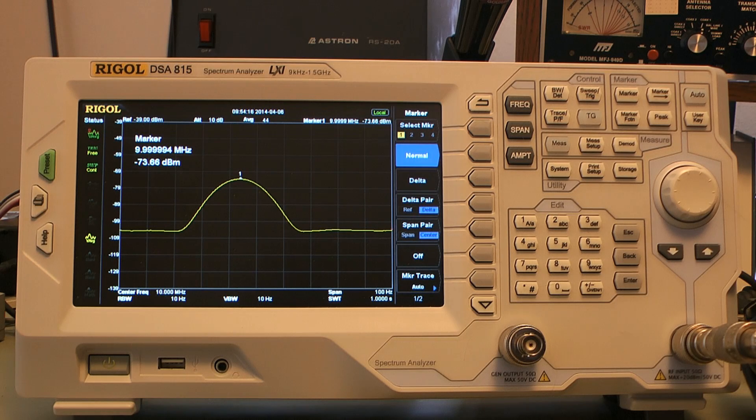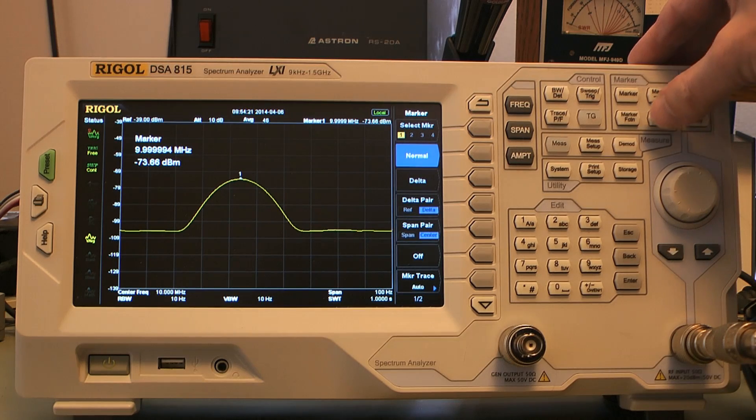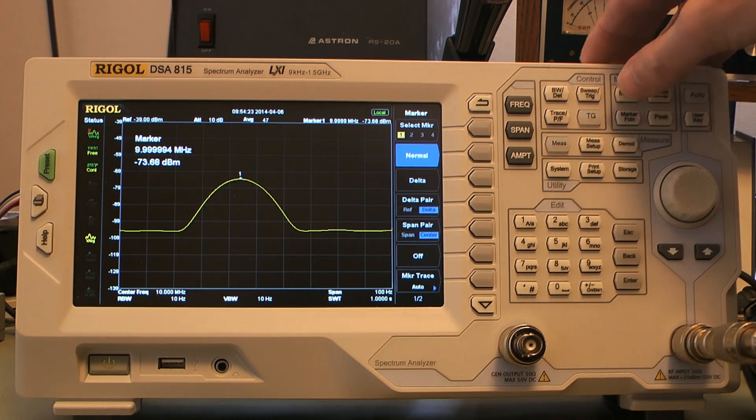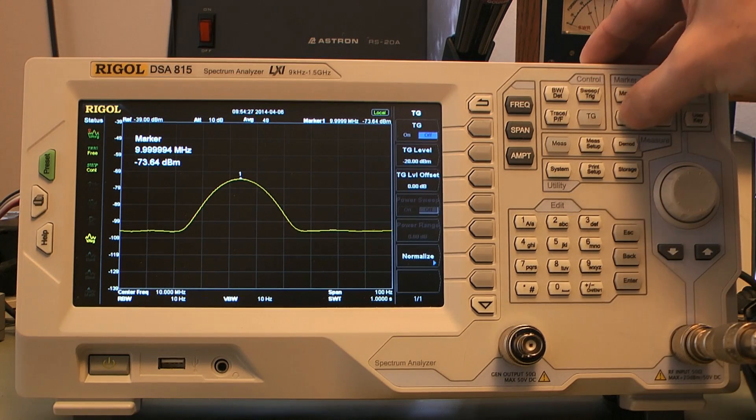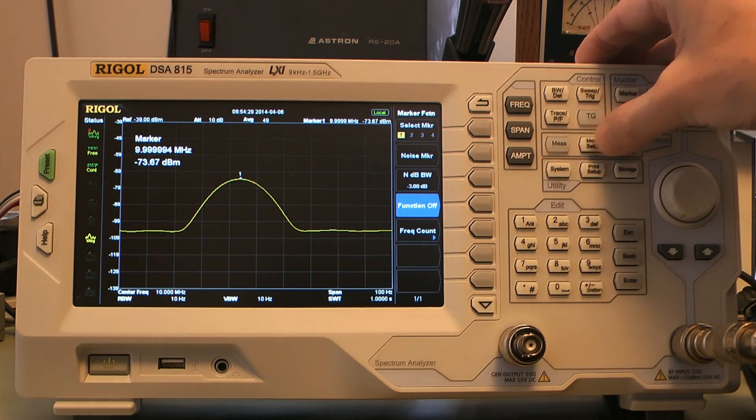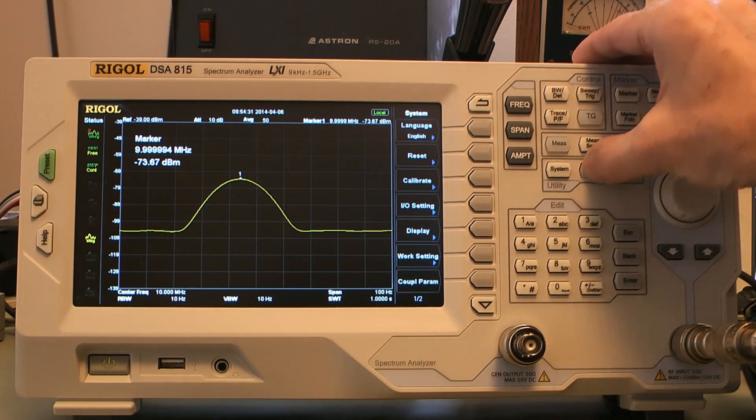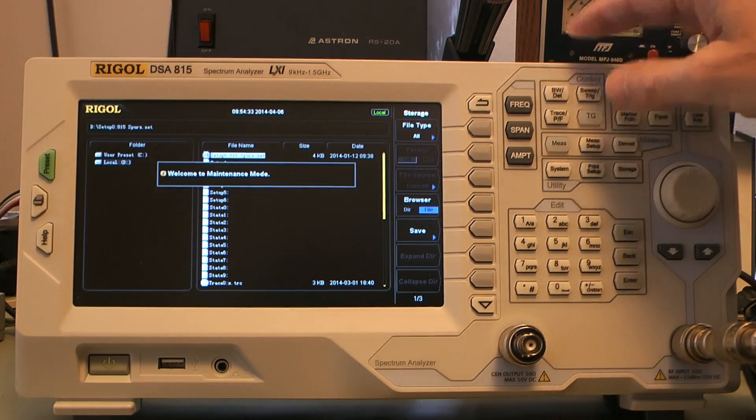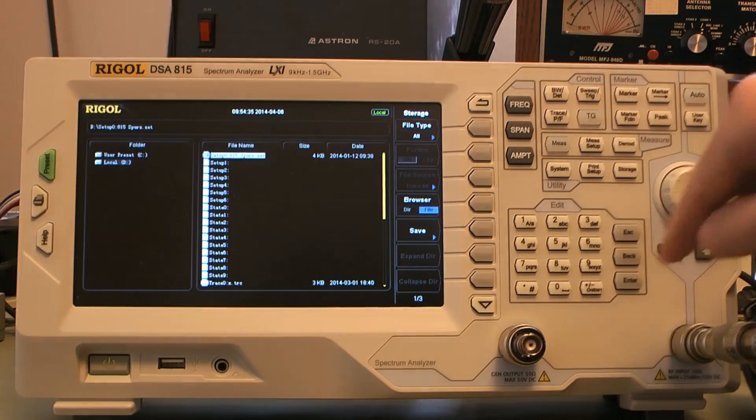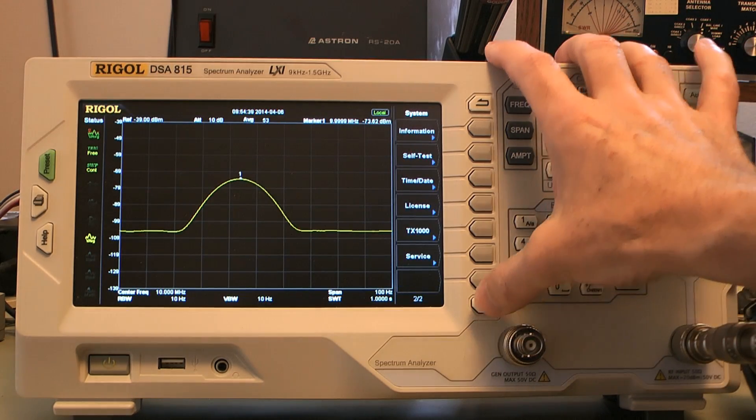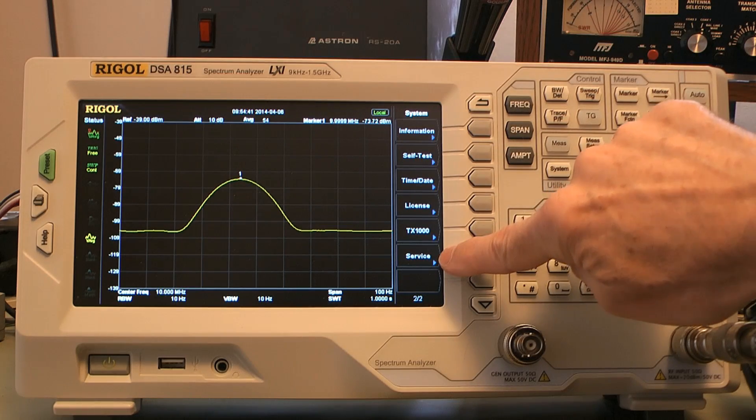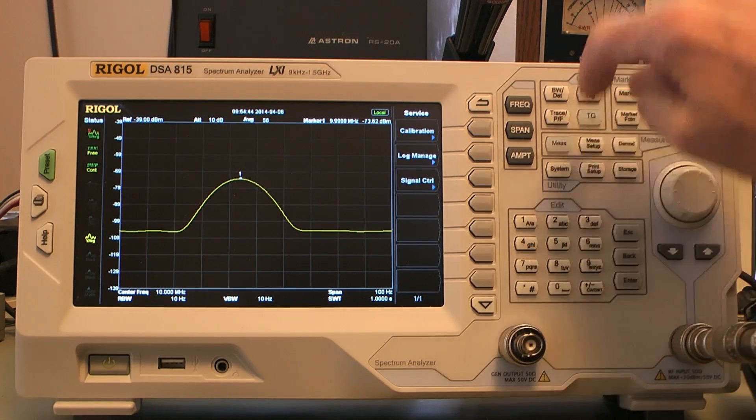Now let's figure out how to get the thing into maintenance mode. There's a pattern of keys that you push that takes it into maintenance mode. So it's trace, tracking generator, marker function, measure setup, system, print setup, storage. And you get a little message, welcome to maintenance mode. Now you can go to system, second page, and there's a new menu item on there called service. Click service, click calibration.